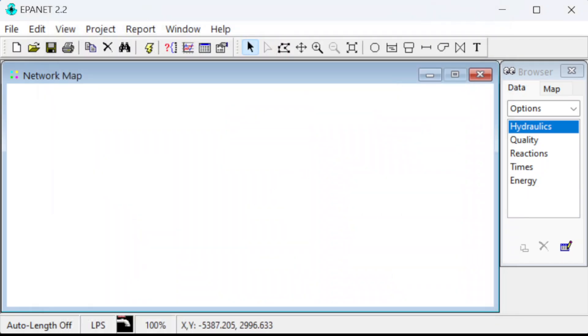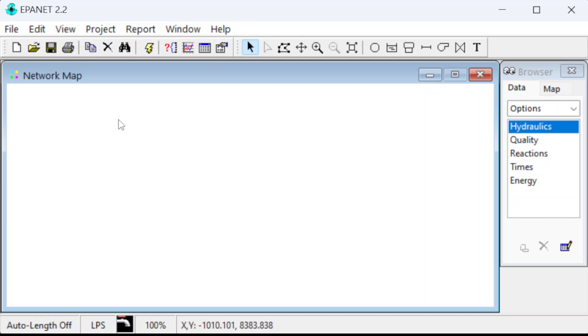The roughness coefficient for Darcy-Weisbach is also in millimeters here, so double-check that for your units. We want to make sure that we put things in that are consistent with that. Our flows are given in liters per second, so we're good there. The diameters are in centimeters, so we need to convert those to millimeters, and the roughness heights are in millimeters, so we're good there.